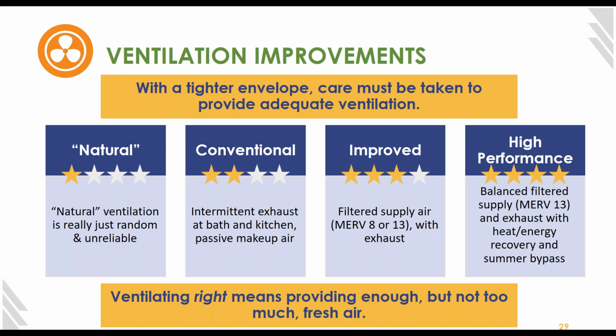Now, on a building with this kind of ventilation, you can still open a window if you want to. But let's say it's a really hot day or a really cold day or the air quality outside is really bad. Here in Northern California, we are experiencing, unfortunately, a lot of wildfires on a not infrequent basis. And there are days when the air quality is just really bad. And if we are building housing and telling people that to ventilate their apartment, they need to open the windows, what does that mean for people during a wildfire situation with unhealthy air quality outside? Or what does that mean for folks with allergies? I really think we should think twice before looking at natural ventilation or even unfiltered ventilation as an appropriate strategy going forward.